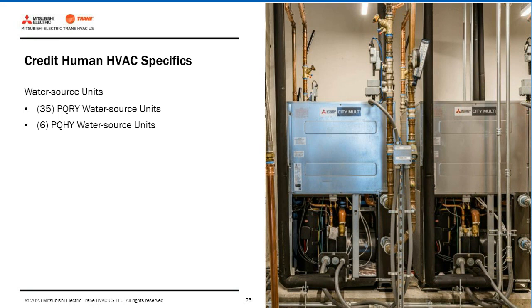So, Credit Human HVAC specifics. This project used a total of 41 water source condensing units, all of which are housed in the mechanical rooms on each floor of the building. The units are stacked on top of each other on some of the floors where we have more than just 4 units. The indoor installation protects them from the elements and maximizes the building's usable outdoor space.